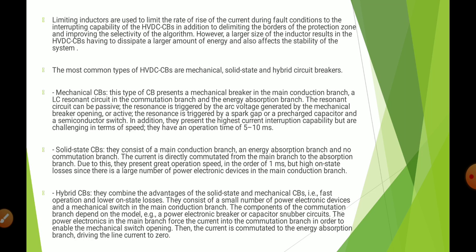Solid state circuit breakers. They consist of a main conduction branch, an energy absorption branch, and no commutation branch. The current is directly commutated from the main branch to the absorption branch. Due to this, they present high operation speed, in the order of 1 millisecond, but high on-state losses since there is a number of power electronic devices in this branch. Even though they provide greater operation speed, due to the number of power electronic devices in the main conduction branch, the efficiency gets lower.